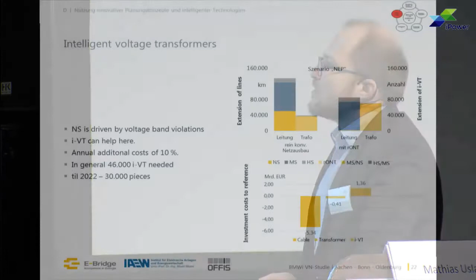It will definitely be better if some things change in terms of ICT. The next step we took into account is, in German, regelbare Ortsnetztrafo, which roughly translates into intelligent voltage transformers. In the low voltage grid we always had voltage band violations in our simulations, and intelligent voltage transformers can help there. Of course, it raises the additional cost for the ICT and the tap changer part of the conventional transformer up to 10%.